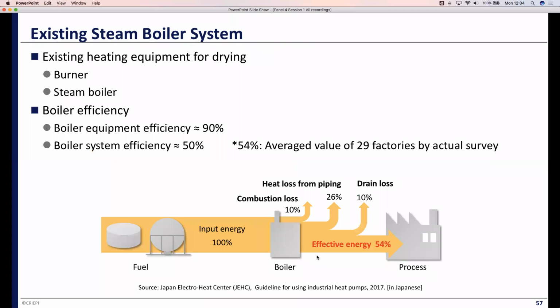Japan Electro Heat Center surveyed the actual condition of steam supply systems. At the average value of 29 factories, the boiler system efficiency was 54%. Not only combustion loss of 10%, but also heat loss from piping of 26% and heat loss from drainage of 10% were revealed.